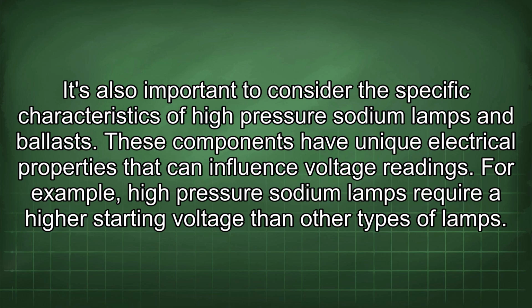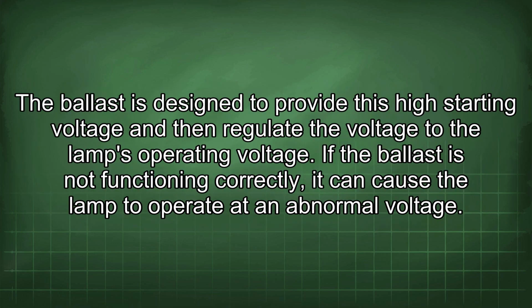These components have unique electrical properties that can influence voltage readings. For example, high-pressure sodium lamps require a higher starting voltage than other types of lamps. The ballast is designed to provide this high starting voltage and then regulate the voltage to the lamp's operating voltage. If the ballast is not functioning correctly, it can cause the lamp to operate at an abnormal voltage.